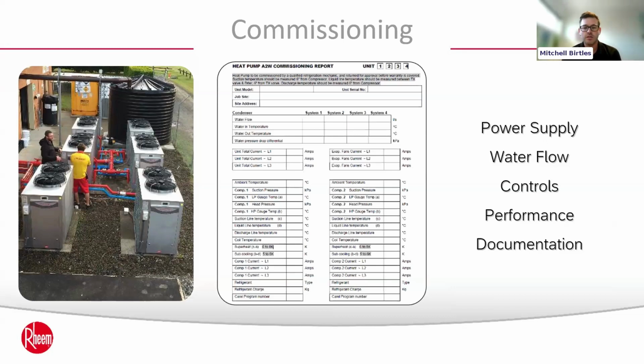Depending on the site, commissioning undertaken by a licensed service agent or the manufacturer's service employee can take around half a day per large unit or multiple banked unit install. We look at many aspects of system setup and performance, and depending on the unit configuration, we may need supporting experts in BMS controls or have the installers ready on site to make the necessary tweaks to water flow or the like to ensure we've got the correct performance settings.